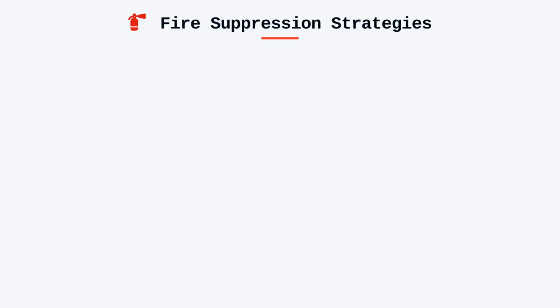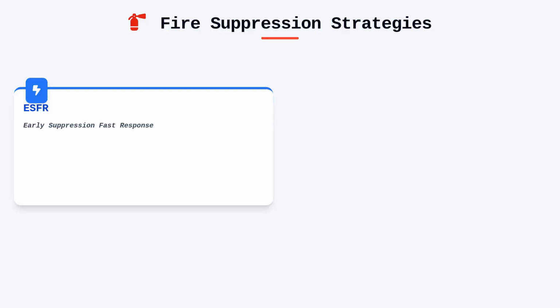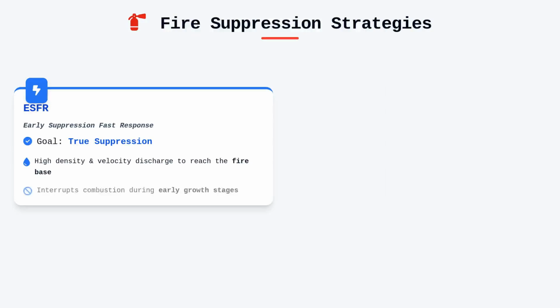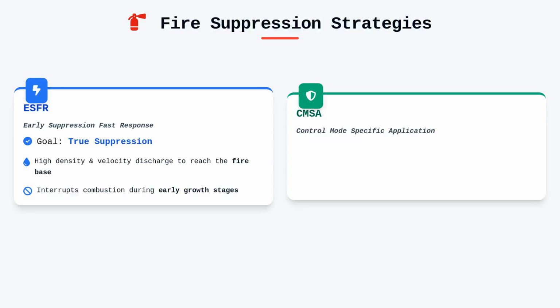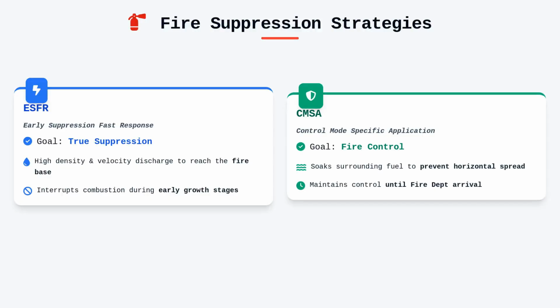Suppression in these environments usually relies on either early suppression fast response, known as ESFR, or control mode specific application, or CMSA sprinklers. The hydraulic demand for these systems is hyper-specific because they are designed to perform a distinct task. An ESFR system aims for true suppression, meaning it must discharge water at a high enough density and velocity to reach the base of the fire and interrupt the combustion process during the early stages of growth. Conversely, CMSA systems are primarily designed to control the fire, essentially soaking the surrounding fuel to prevent horizontal fire spread until the fire department arrives.